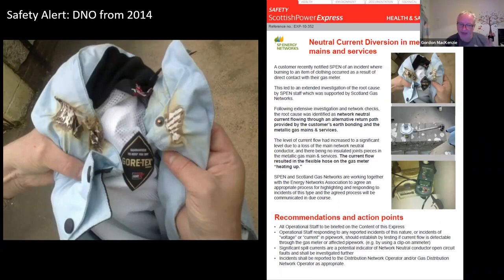The network itself was an interconnection, an LV main interconnected between two substations with a couple of wee branches, feeding about 72 properties off that. But it was one of these aluminium neutral earth conductors that ran through the main, and it had failed in multiple positions. I think by the time the guys had got to joint number 7, they gave up on the fact that there was no neutral in the main at all. But there were no flickering light calls. There was no indication for any of the customers that there were any issues until the customer's jacket fell off the hook in that property, landed on the gas meter, and proceeded to go on fire. And fortunately, the customer was in, smelt the burning, and managed to get there pretty quick.